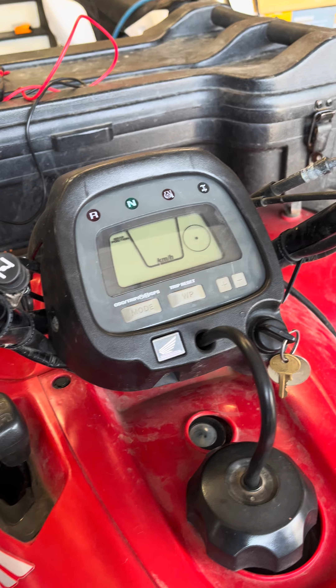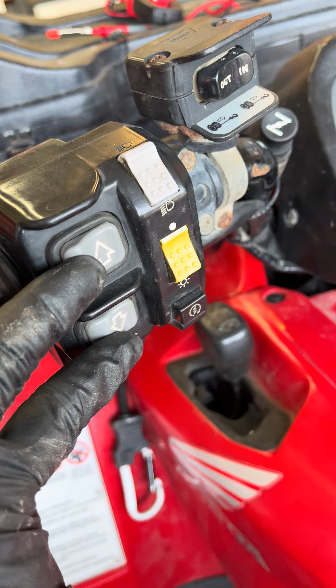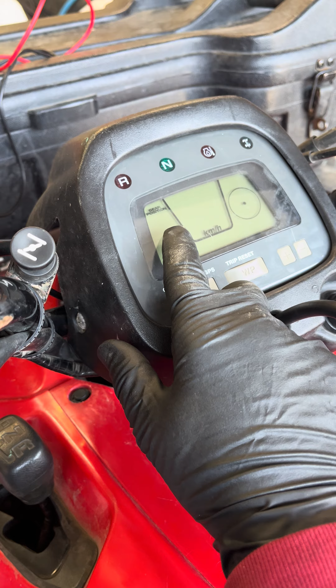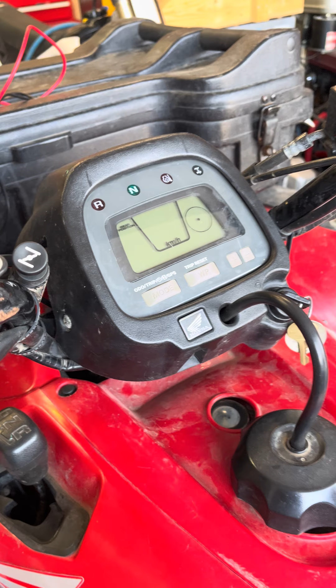Second step: make sure it's in auto again. Don't just turn the key on - when you turn it on, hold up and down, push nice and hard, and turn the key on with the other hand. As soon as you see N on the screen start flashing, let go of the switches and do the combination: up, down, up. Let go. The flashing will go from N to some lines, and it will stop and either show N or alternate between N and two lines. That's how you do the initialization.